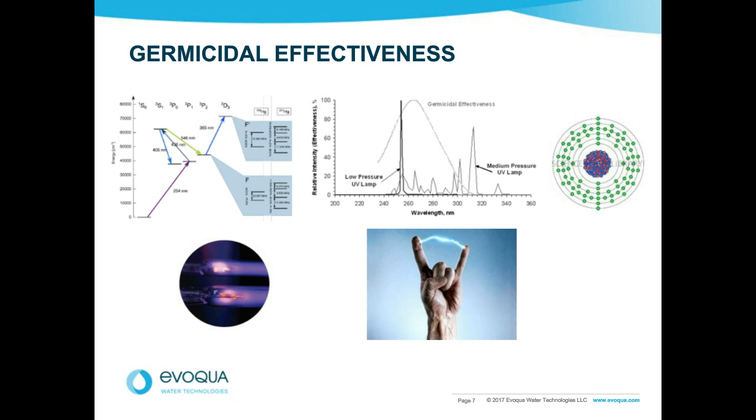The repair mechanisms are documented, but they are limited to low pressure light in sunlight and linked to very low doses. So really the trick is use a validated UV system. A dose delivered to all the water is known to be a certain number. And that takes away all the guesswork.